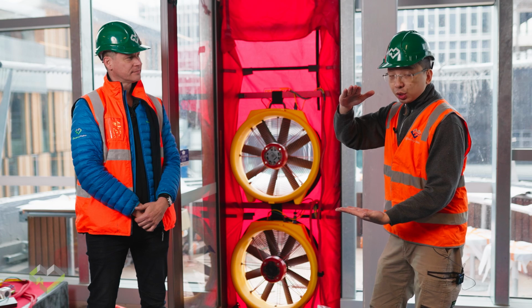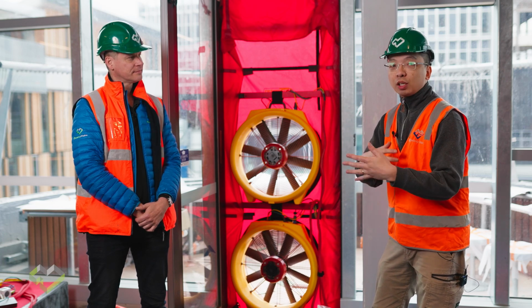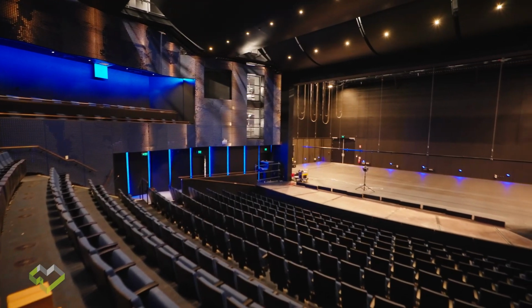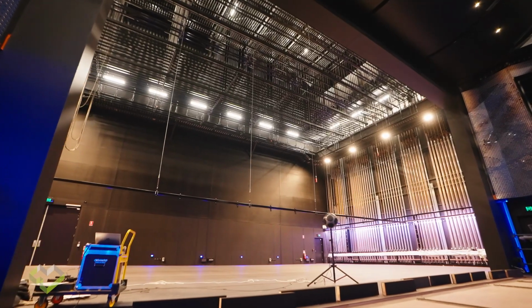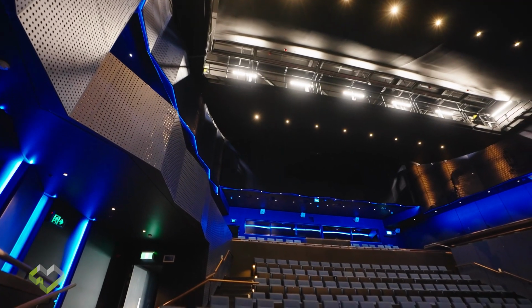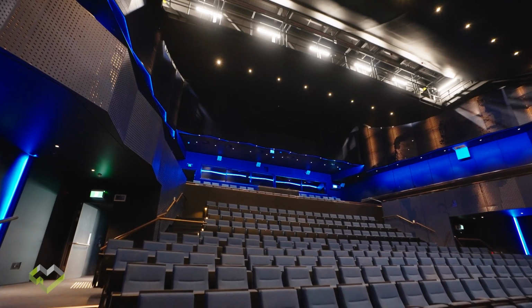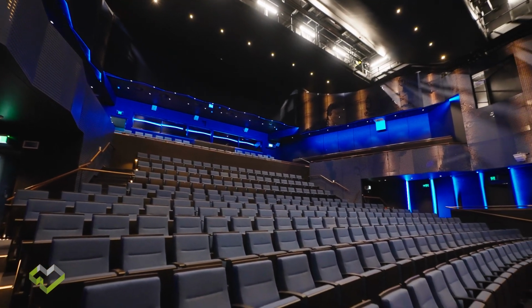What it is useful for is the mechanical designer, because they are typically designing with how many times they need to bring in the outside air for fresh air, or how many times they need to recirculate the conditioned air to provide a comfortable environment. That's why the number of air changes per hour is more instinctively understood by the mechanical consultant.